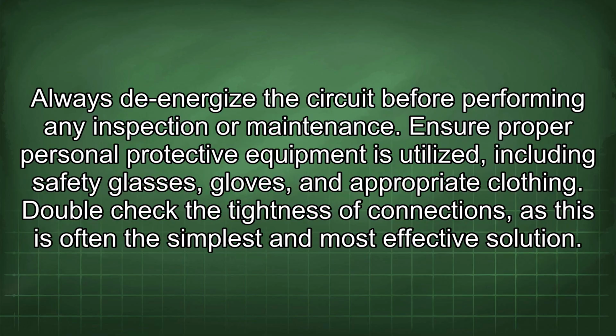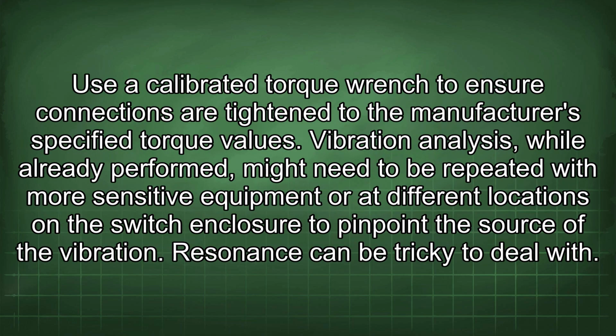Always de-energize the circuit before performing any inspection or maintenance. Ensure proper personal protective equipment is utilized, including safety glasses, gloves, and appropriate clothing. Double-check the tightness of connections, as this is often the simplest and most effective solution. Use a calibrated torque wrench to ensure connections are tightened to the manufacturer's specified torque values.